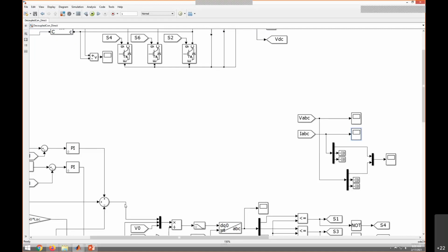When you turn off, we need to discharge the capacitors. Otherwise, if you touch the inverter terminals even though the power is off, you can experience some shock. So therefore, we need to discharge the capacitor through these bleeder resistances. So when you are operating again, it will act as a capacitor with uncharged voltage.